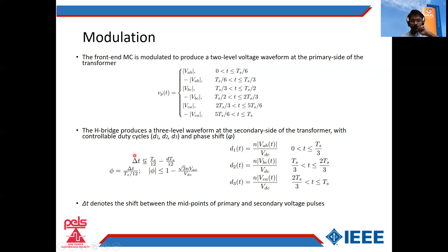That is, for the first Ts by 3 period, you have a ratio of the line to line voltage VAB and VDC, whereas it switches to VBC and VDC, and then in the third one third of the cycle, the ratio is between VCA and VDC. So these duty cycles would be different in each one third of the cycle, and the phase shift can be calculated according to the power requirement, where delta T denotes the shift between the midpoints of the primary and secondary voltage pulses.